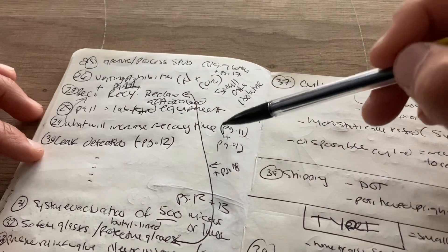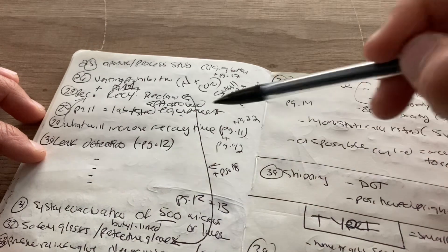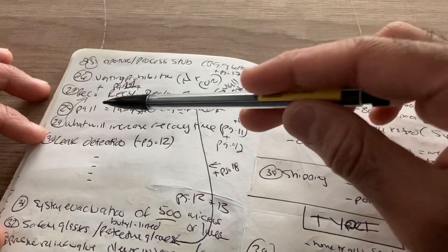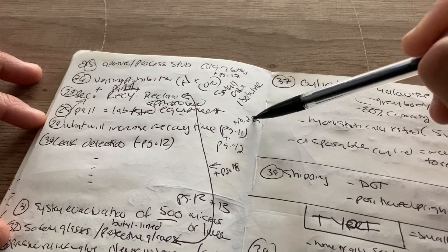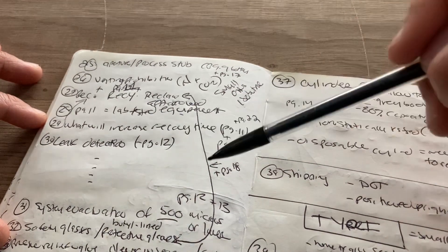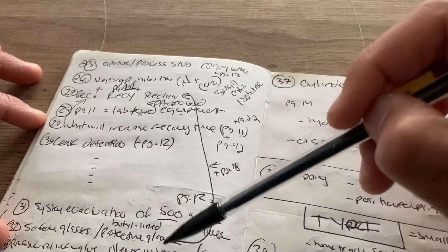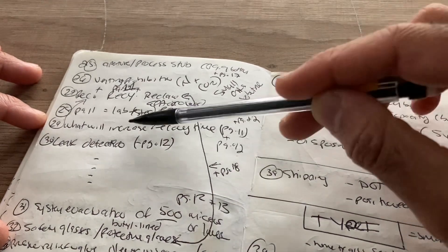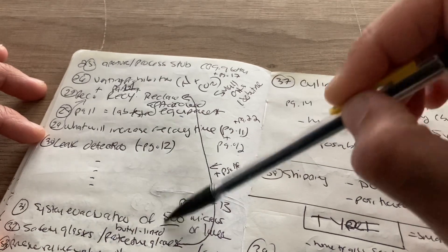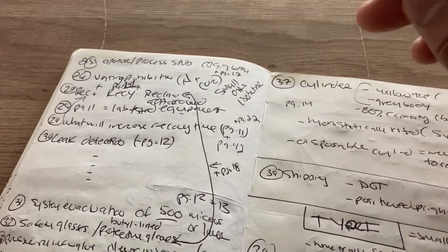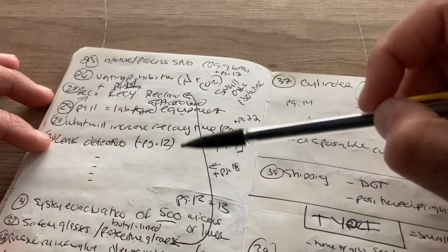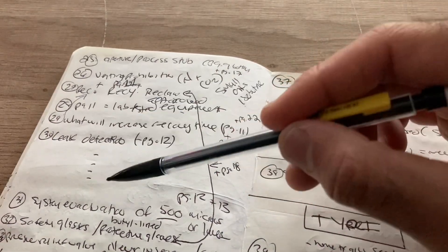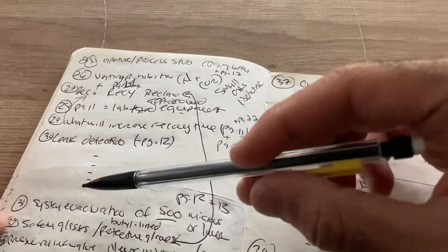All right, what will increase recovery time? There's a few things, but especially on page 11 and throughout the manual, what will increase recovery time? So page 11 and page 22, they talk about that leak detection. Page 12. So the different ways, page 12 and also page 18 leak detection system evacuation. So when you see 500 microns, this is the answer for, if you see microns, 2000, 100, a lot of times the answer is going to be 500. So that's what system evacuation of 500 microns or less. You're going to see that a lot, 500 microns.